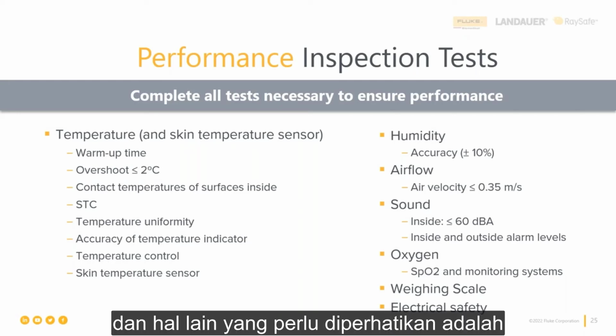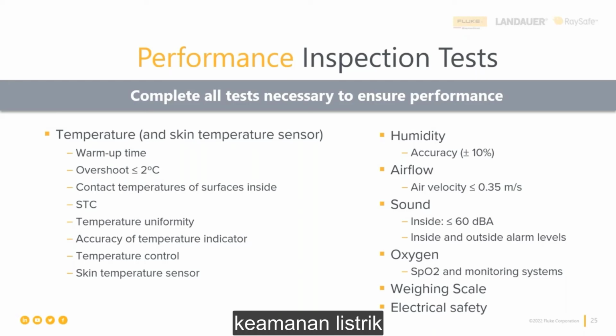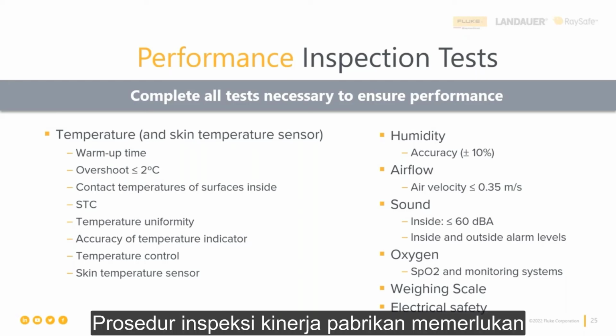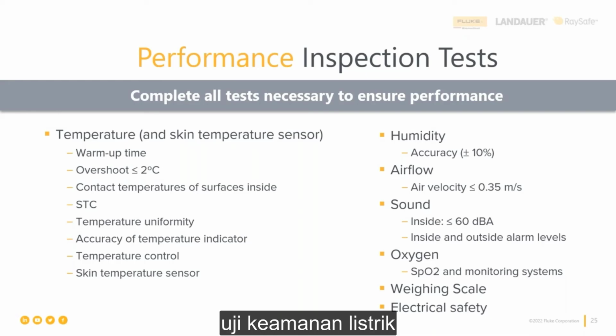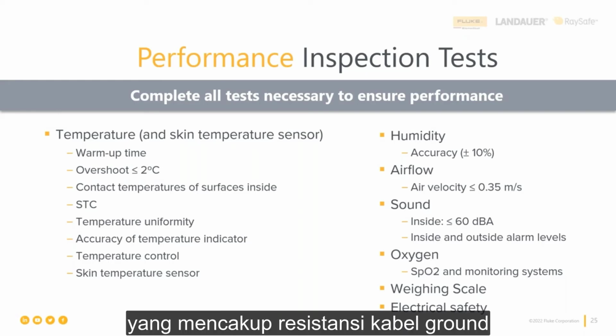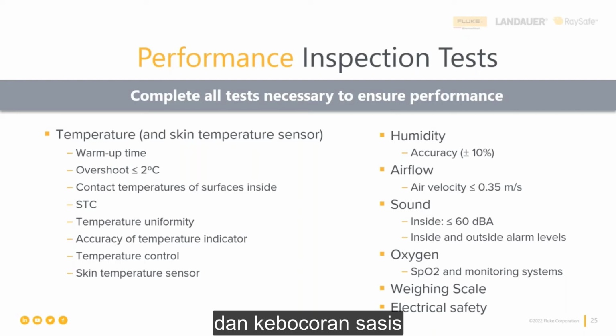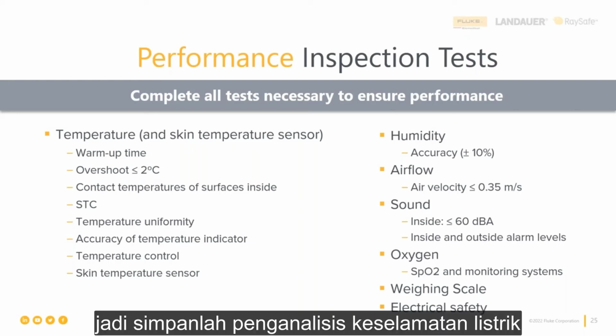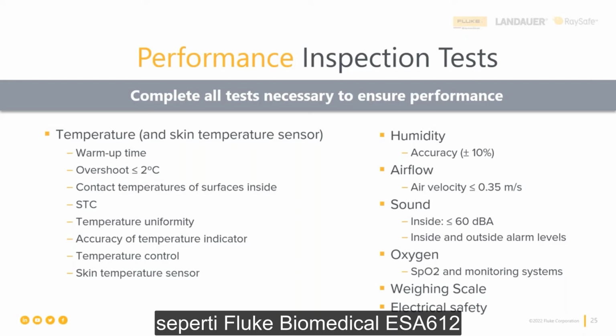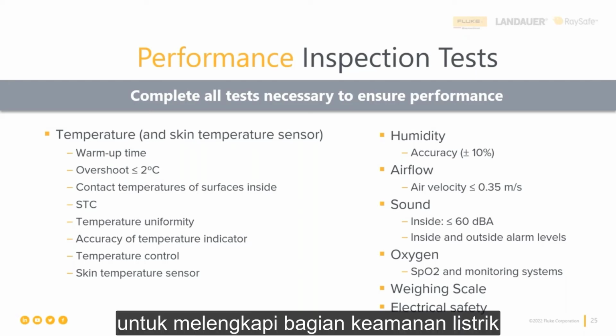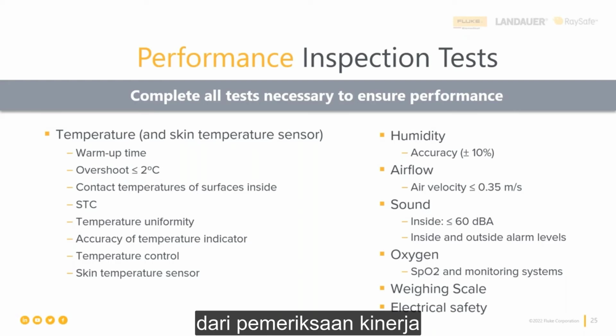And the other thing to note is electrical safety. So most manufacturer performance inspection procedures require an electrical safety test, which includes ground wire resistance and chassis leakage. So keep an electrical safety analyzer like the Fluke Biomedical ESA 612 close by to complete the electrical safety portion of the performance inspection easily.